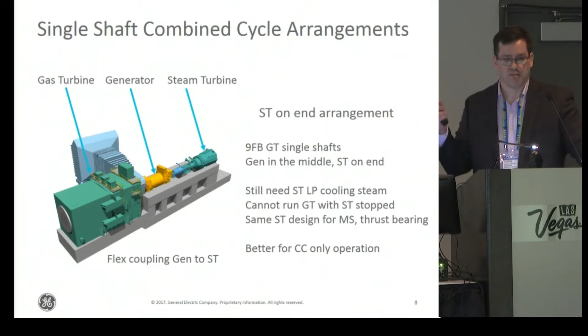On our earlier designs, we did not have a clutch between the steam turbine and generator, and with the flex coupling, whenever you started the gas turbine the steam turbine was always along for the ride. When you're at synchronous speed with no steam going through the steam turbine for power generation, you start getting windage heating on the last stage buckets. Because this heating could damage the buckets, we have to put some cooling steam through to take that heat away. That requires a larger aux boiler, which means more CapEx, more capital expenditure on the power plant.